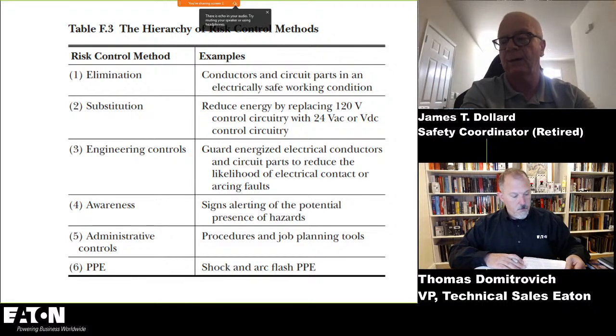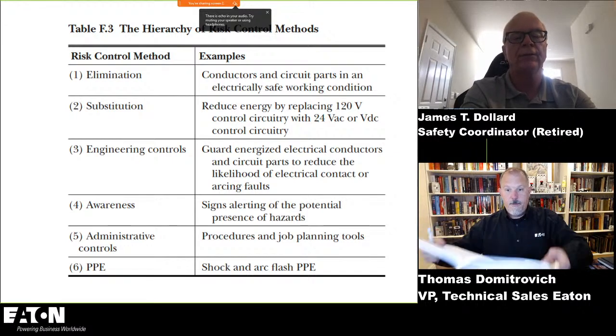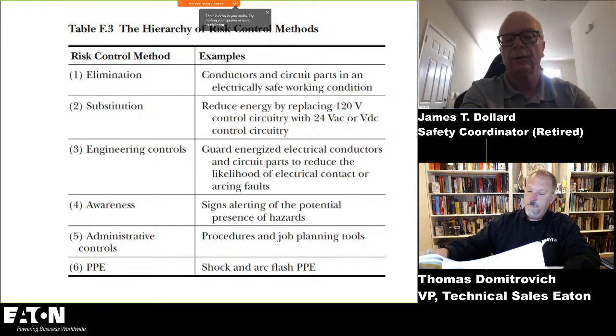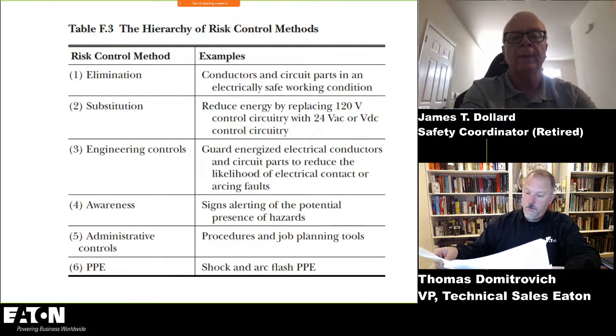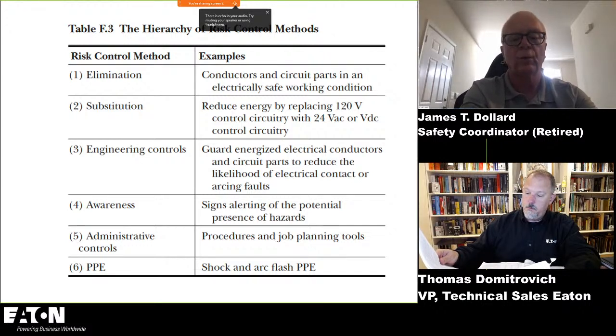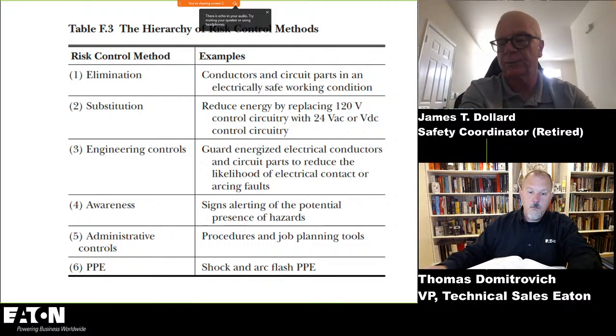There's a significant amount of great information in the annexes, and here in Table F3, elimination is conductors that are placed into a state that we call an electrically safe work condition. Substitution, instead of 120 volt control, use 24. Engineering, you could guard energized electrical conductors. Awareness, it would be signs. Administrative controls is procedures, job planning tools, training, and much, much more. And then PPE is just that, shock and arc flash PPE.